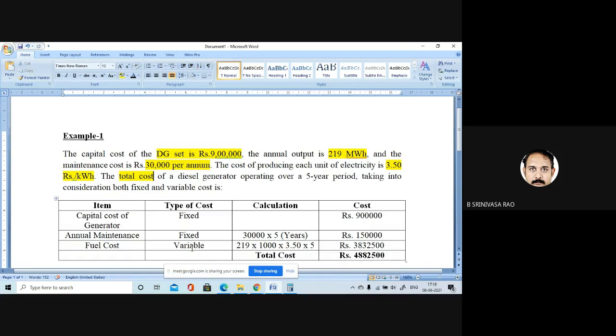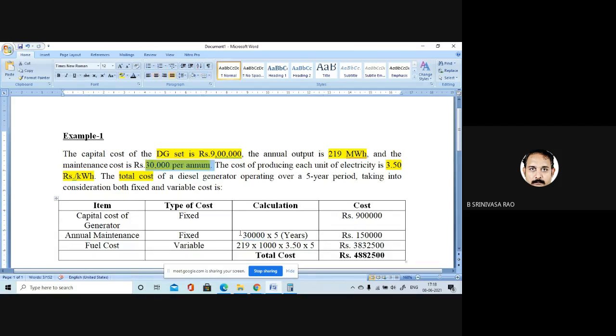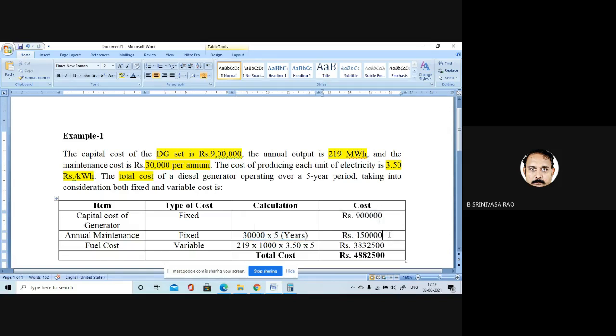We have to bifurcate — divide which cost is fixed and which is variable. The capital cost of the generator is fixed cost: 9 lakhs. The annual maintenance cost is also coming under fixed cost — 30,000 per year. So for five years, the annual maintenance cost is 1,50,000, which also comes under fixed cost. The fuel cost is your variable cost, as it totally depends upon the annual output. If the output changes, the fuel cost will also change.